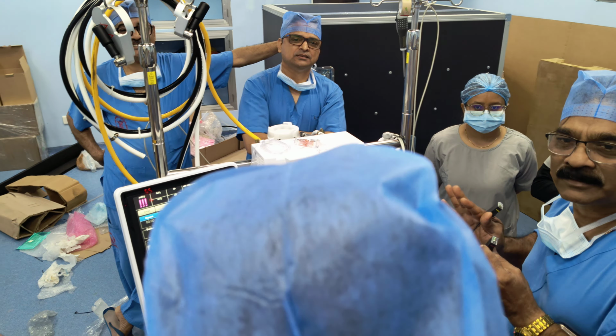So this is as far as the level is concerned. The level sensor, however, if you click in the middle of it, you see a level. When I put disabled, it will disable. Now it is disabled. That's why your pump is running. The minute you want to activate it, put protected flow. Now it is pump stop. You saw? Now it is telling you that there is no level sensor. However, anytime while on bypass, just press disable.